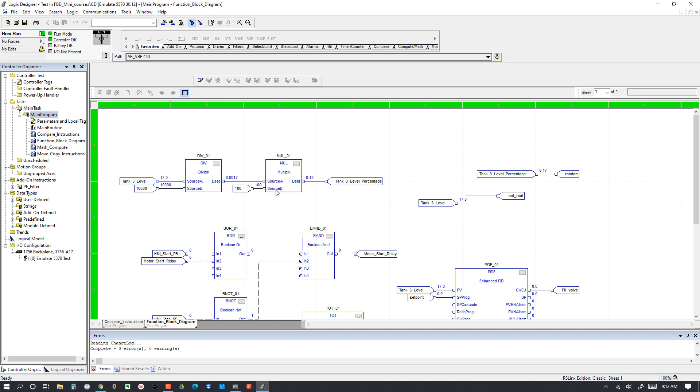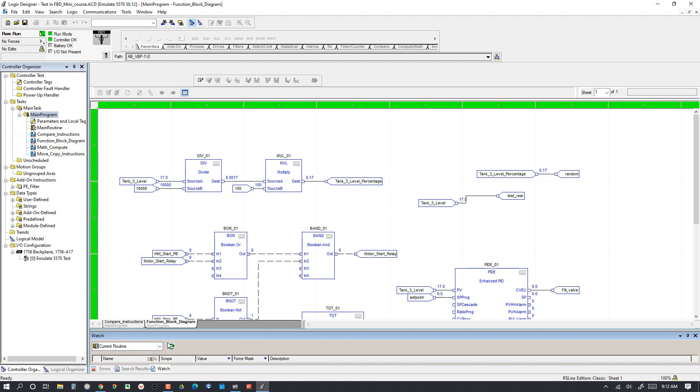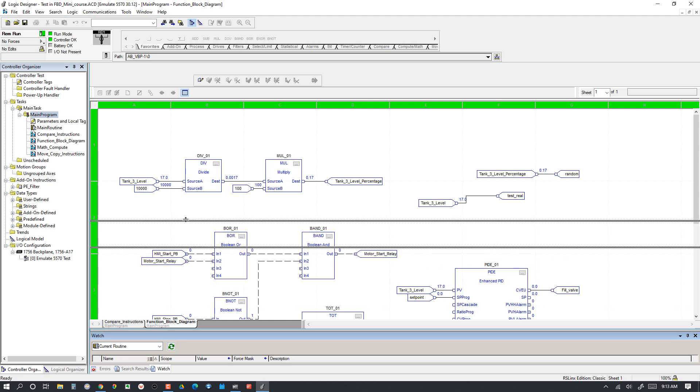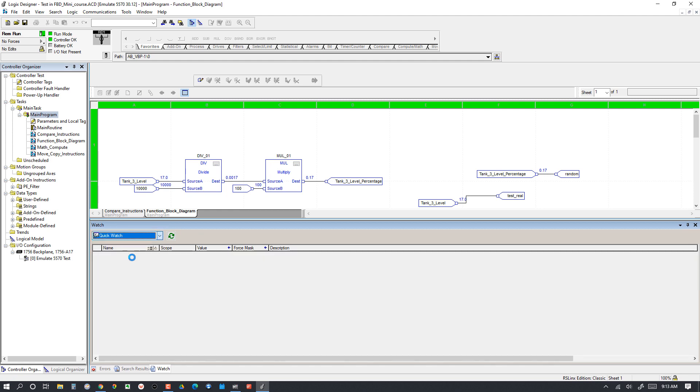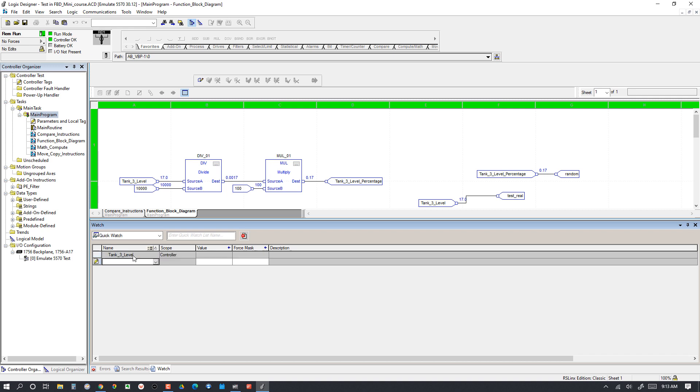In this case, we're taking 0.0017, connecting it to the destination of the Divide, connecting it to the Source A of the Multiply. Then in the Source B of the Multiply, we've got the number 100. We're multiplying by 100 to give us a percentage. Let's pull up the watch window here and I'm going to do a quick watch so we can look at only the tags we care about right now: Tank 3 Level and Tank 3 Level Percentage.